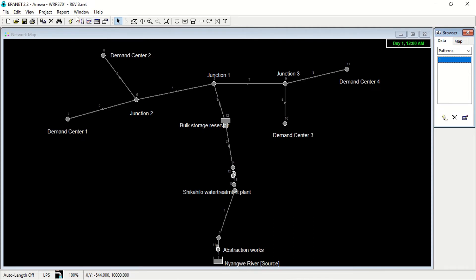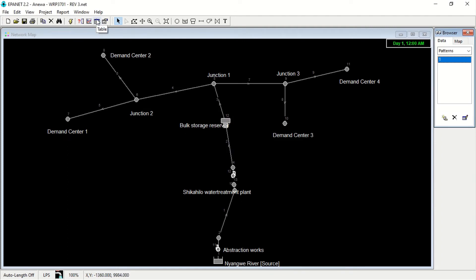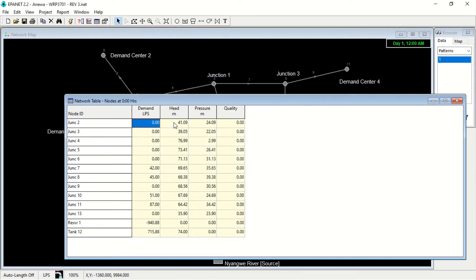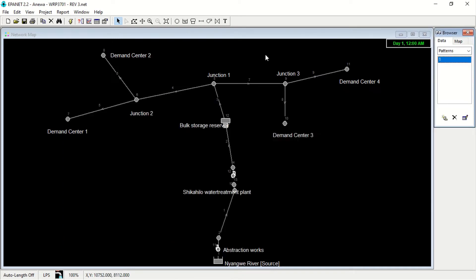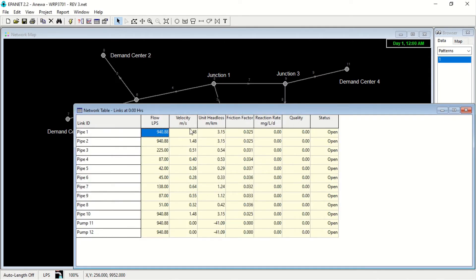When you run the program, it ran successfully. The first time I ran it with the 300 millimeter pipes, the run was not successful — I was getting negative pressure and the velocity was too high. So I had to adjust my pipes. When you go here, you can see the pressure head is not negative, so everything is fine. Then you check the network links and you can see the velocity is not negative, which is good.